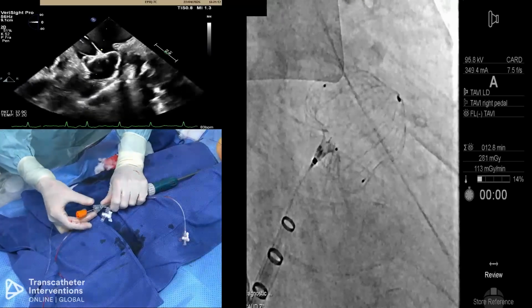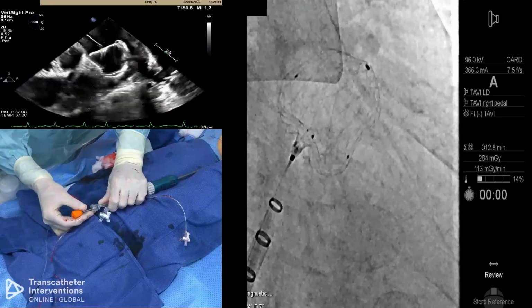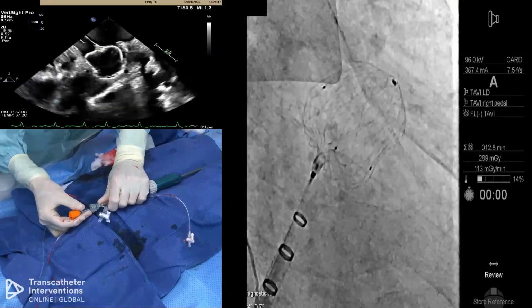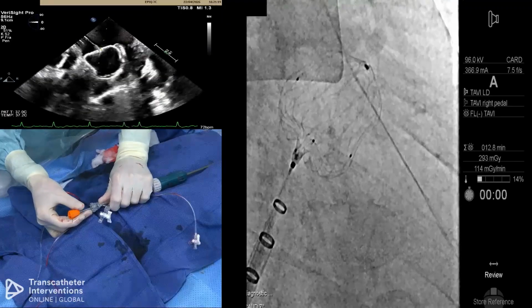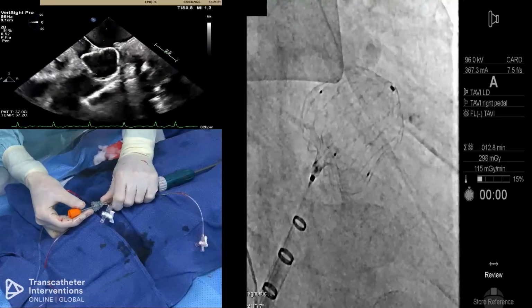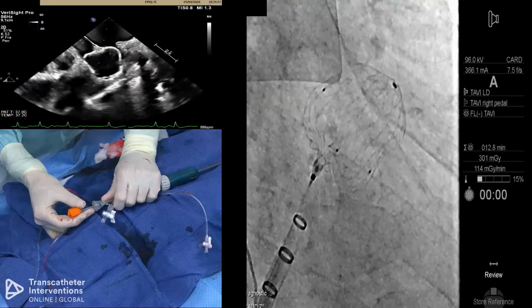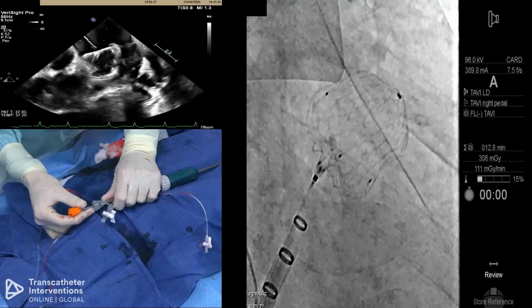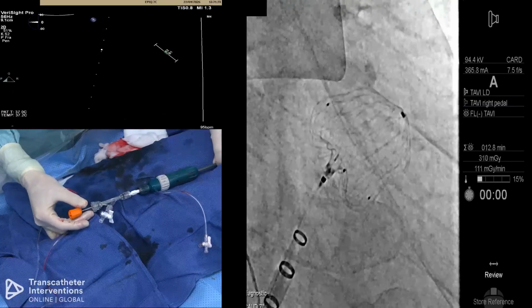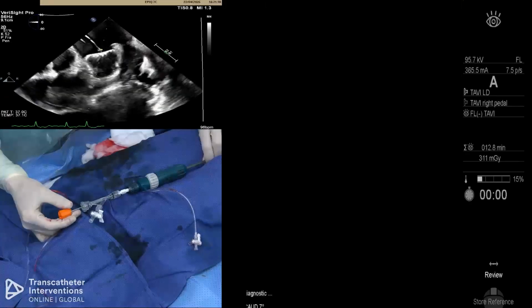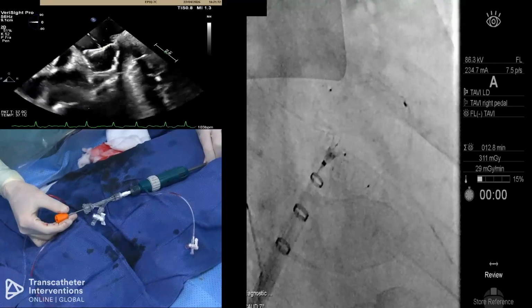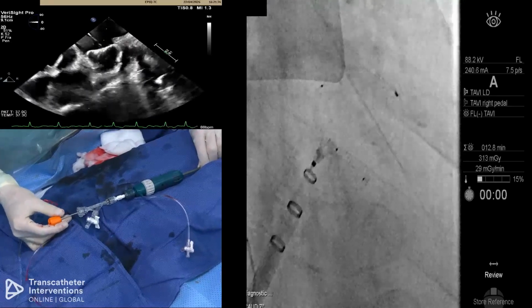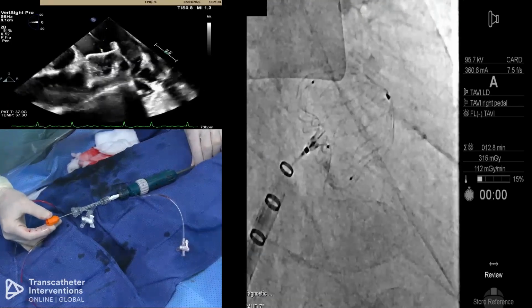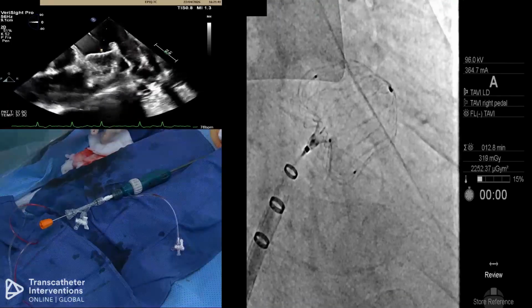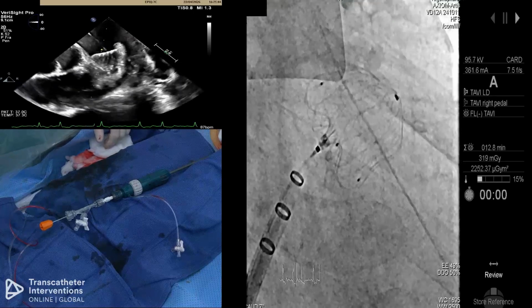And typically it's a gentle tug. I'm not tugging extremely hard on this. So this is enough. You see, I'm pulling as long as that small waist is out. So now the waist on the proximal part of the device is out, and this is enough. I don't think it moved at all. No. And now I'm pushing the device, and look, it looks very stable. Push. You see, then I get that waist on the proximal end of the device again. So to be honest, in summary, I think it sits good.